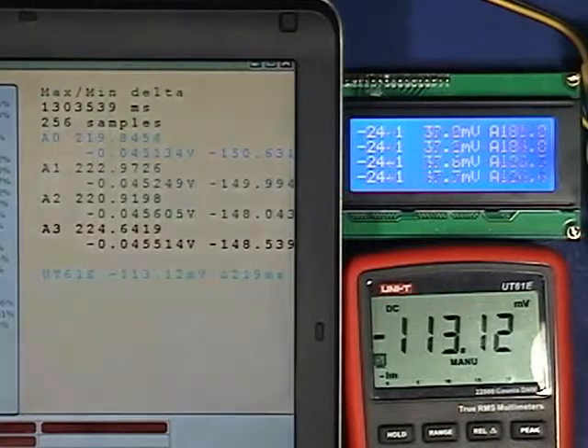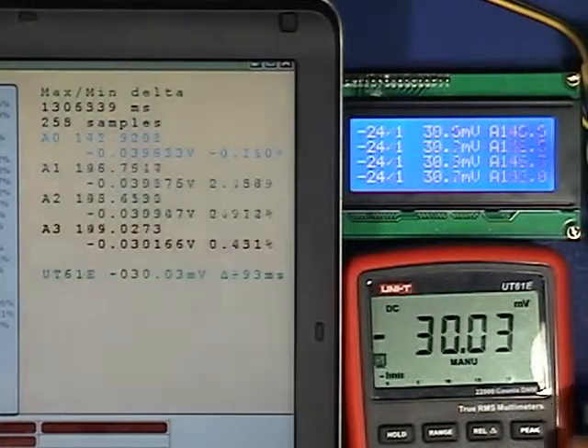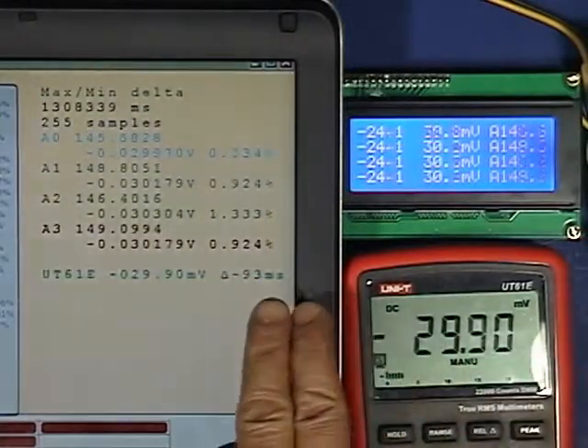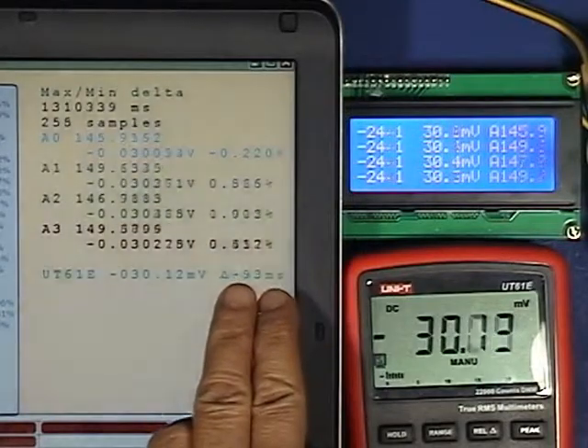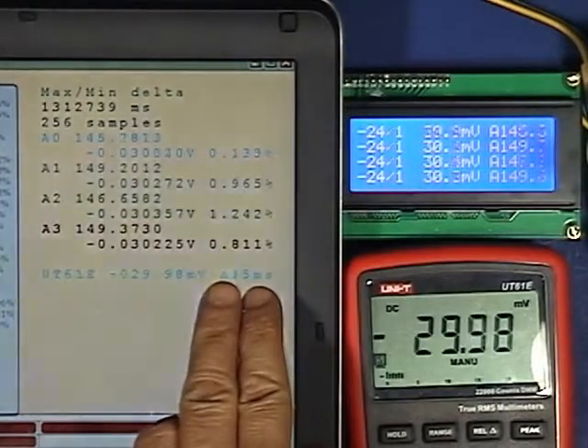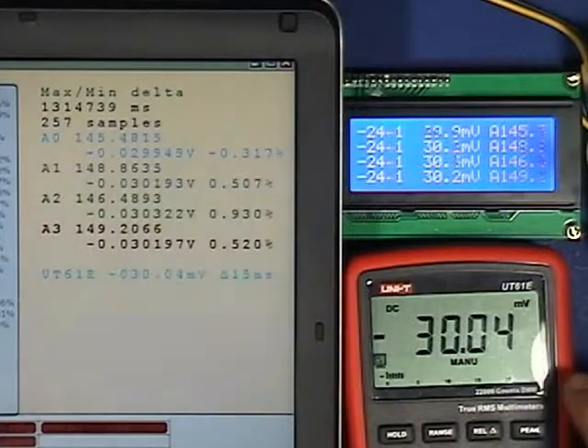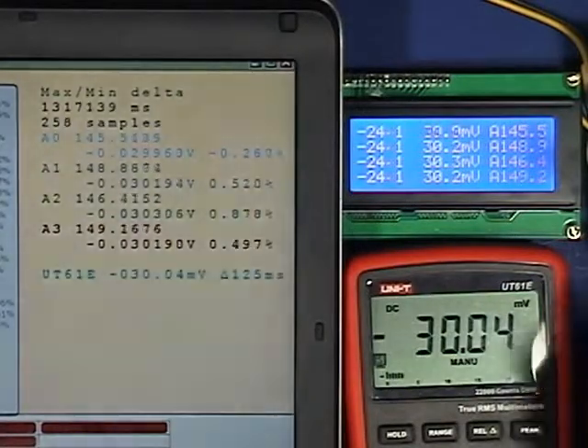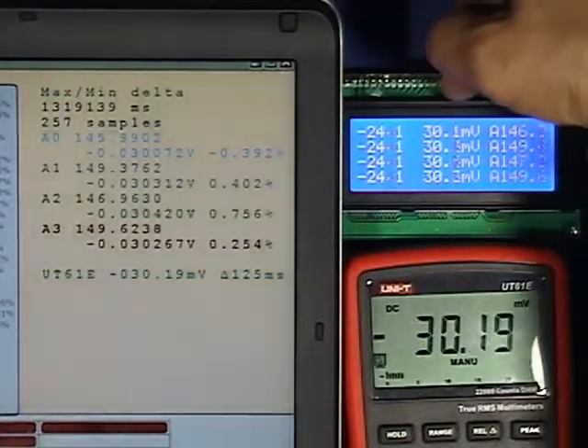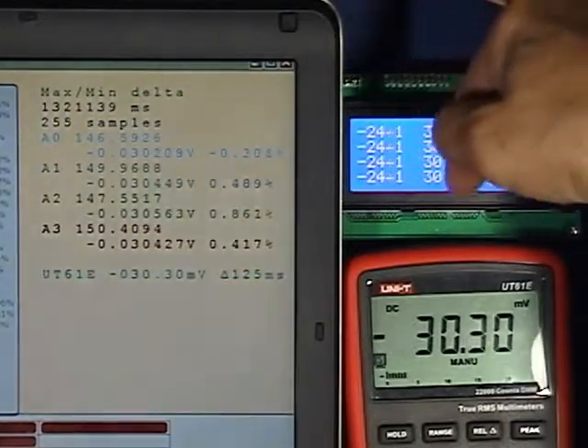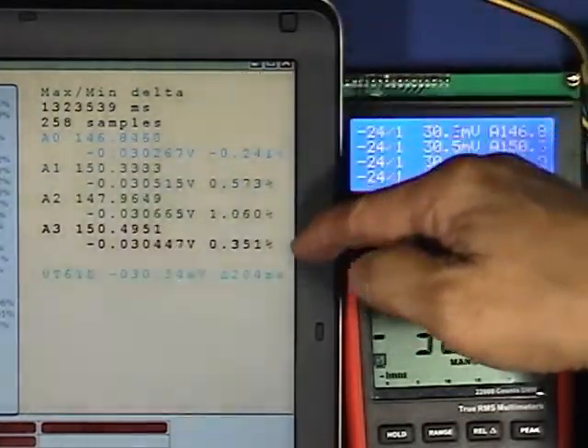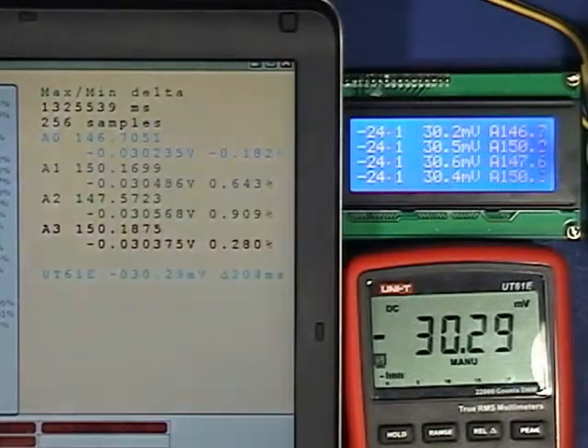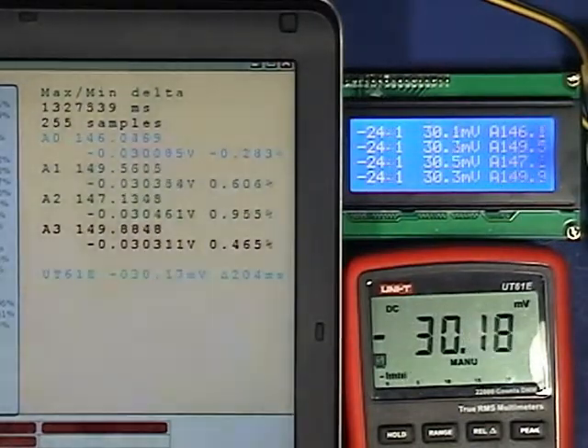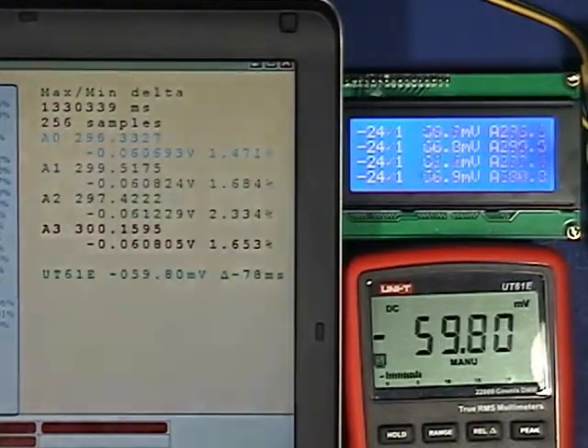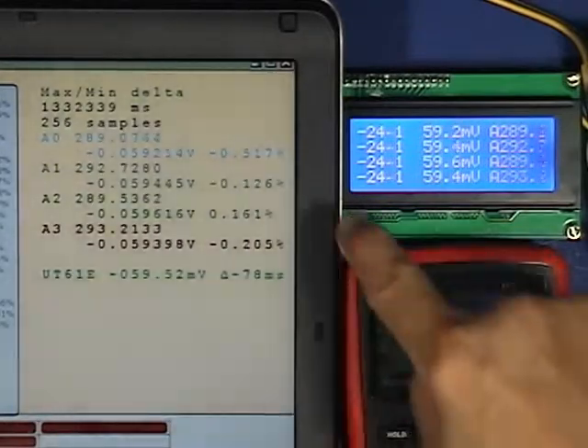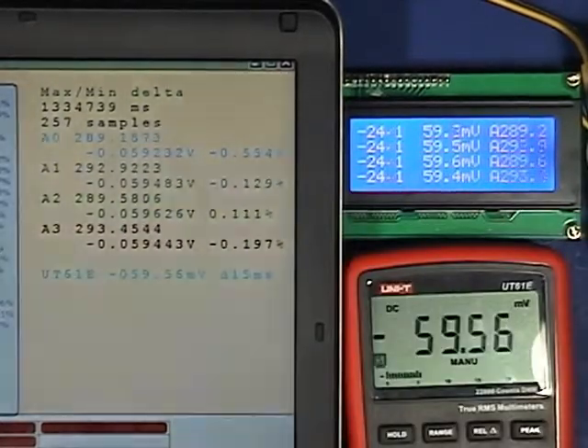Minus 30 millivolt, you start to go below 1% error. Almost on the dot. 30.04, 30.1, 30.2, they're all below 1% error or twitching around 1% error. Then as you go up to about 60 millivolt, they're all below 1% error.